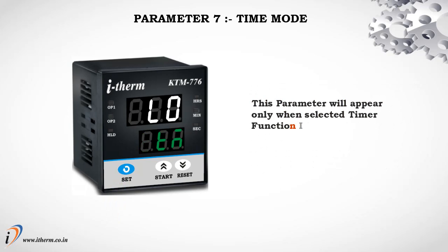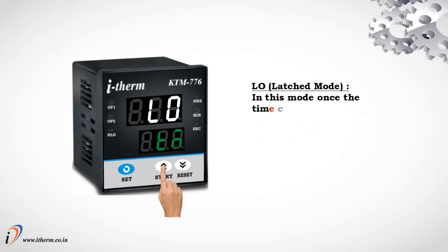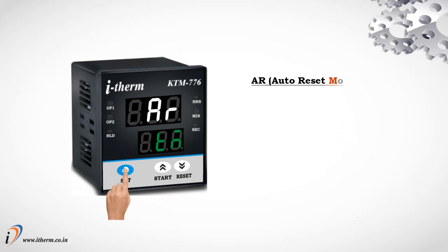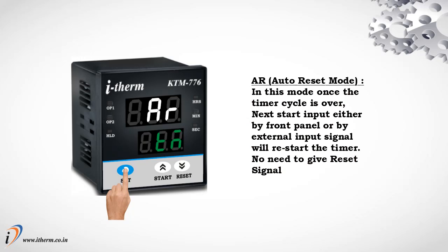Parameter 7: Time Mode. This parameter will appear only when the selected timer function is On Delay or Off Delay and the start input is other than Power On Start. Latched Mode: once the time cycle is over, the user must issue a reset signal from the front key or external reset input to restart the timer. Auto Reset Mode: once the timer cycle is over, the next start input — either by front panel or external input signal — will restart the timer.